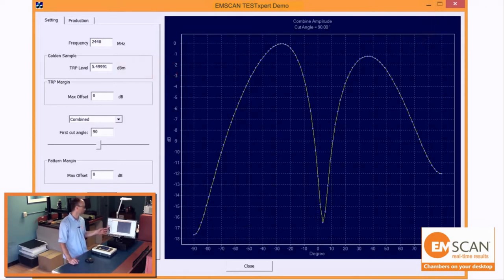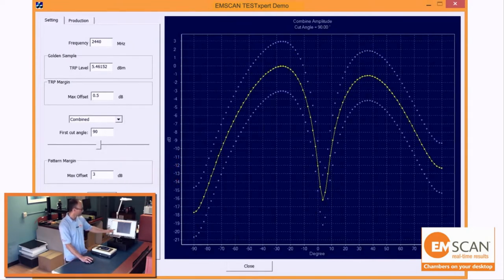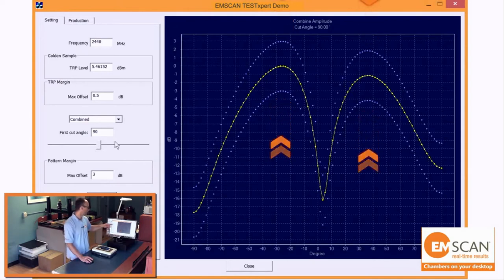Now that those levels are established, we can set the margins: 0.5 dB, and for pattern margin we'll allow a bigger margin of 3 dB in the pattern. This shows us the threshold for pattern and power level.